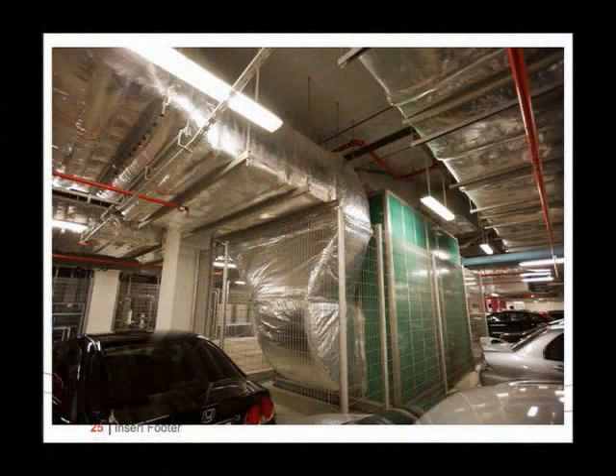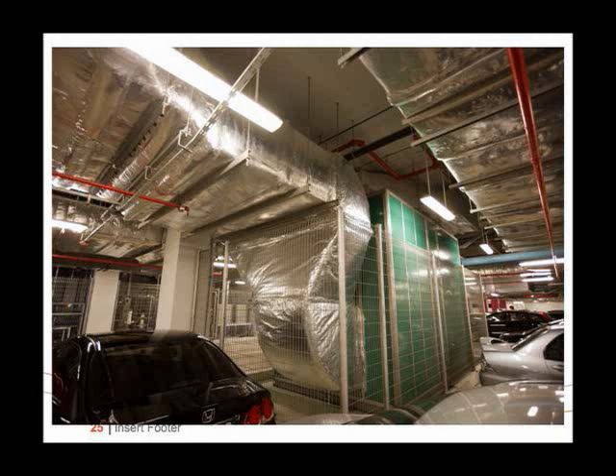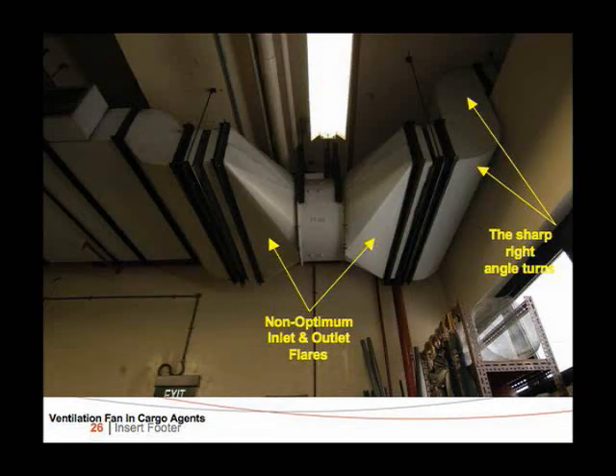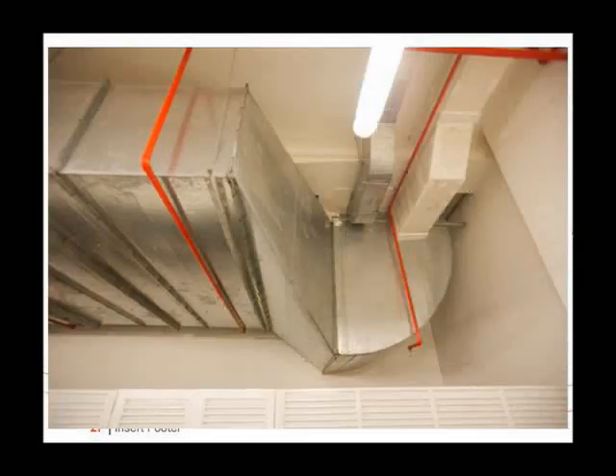And here is a design engineer's issue. You have a fan, air handler, with a fan discharging at low level, which then has to make a heroic turn and another heroic turn with a gigantic flare here. You can specify air handlers with a discharge on top, and then you avoid all the heroics. You just have to call TRANE, 1-800. This is from the airport, and everywhere you go, there are these heroic flares. You should not have symmetrical flares. Huh? The discharge should be a lot longer. Right angles, etc., etc. One of our platinum-rated buildings in Singapore, you know, another heroic turn from the...